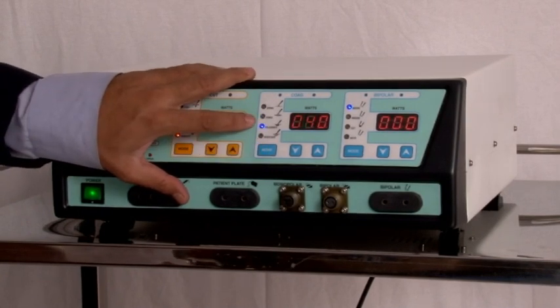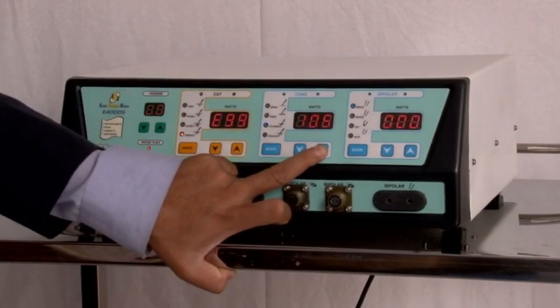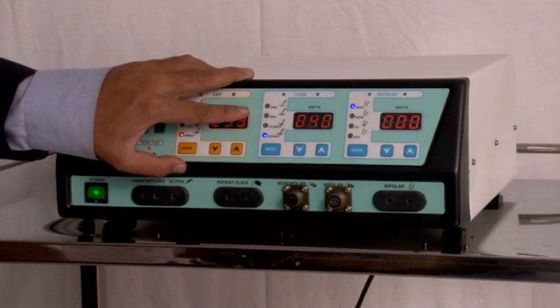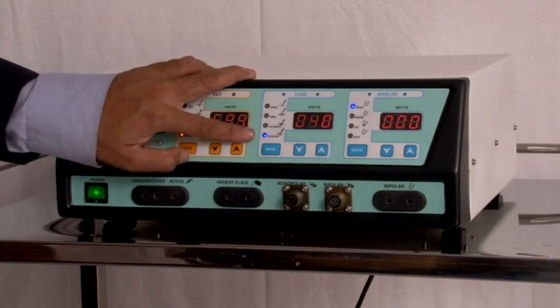Third mode in coag is fulguration, a non-contact coagulation effect with modulated sine waveform, which assures fast coagulation of the tissues and can be used in all types of surgical procedures. Fulguration has a maximum output of 150 watts. The last mode in coagulation is desiccation, pure sine waveform with lower peak voltages, which assures coagulation at superficial levels by contact coagulation method. Desiccation is preferred by neuro, ENT and endoscopy surgeons. Desiccation has a maximum output of 150 watts.